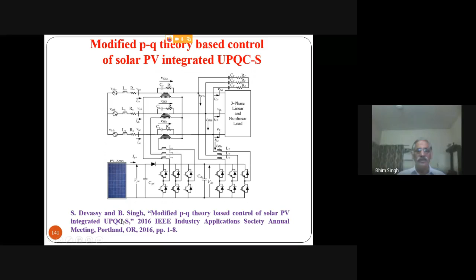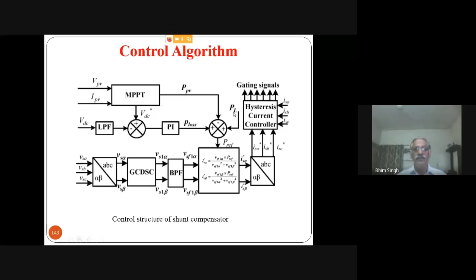This series compensator also does the load balancing, harmonic compensation, as well as reactive power compensation. Here we use the modified PQ theory, the instantaneous reactive power theory, given by the Japanese group, the Akagi group, which has a book as well as probably hundreds of papers in power quality, so that's a modification of the control for the shunt compensator along with the solar power generation.